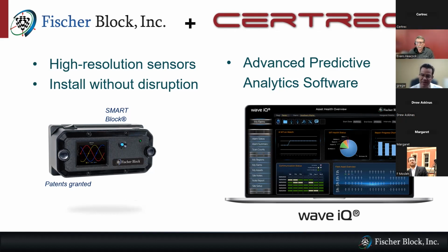But that device is intelligent enough to ascertain when things are getting out of the norm. And when those conditions arise, that device then will capture the electrical signatures and send them off to the software platform, WaveIQ, which then does further analysis, compares signatures against historical norms, either for that particular device that sent in the file, or against sister devices, data files, and histories, and then presents that information in terms of actionable insights on various dashboards. There's communication alert notifications as well.